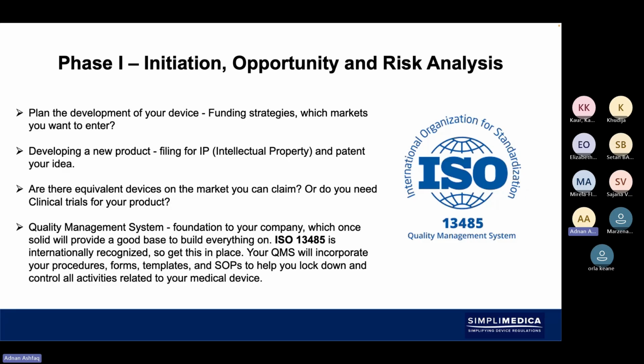The recent revision was 2016. It will be revised again probably in the next year or so. There's been talk about it being revised in 2026. There was an addendum that came out in 2021, which was specifically to align it to the European medical device requirements, so the EU MDR 2017/745 and the IVDR 746. There are some specific annexes which were added on to the 2021 revision of ISO 13485, which make sure that you're also aligned to the European regulations.